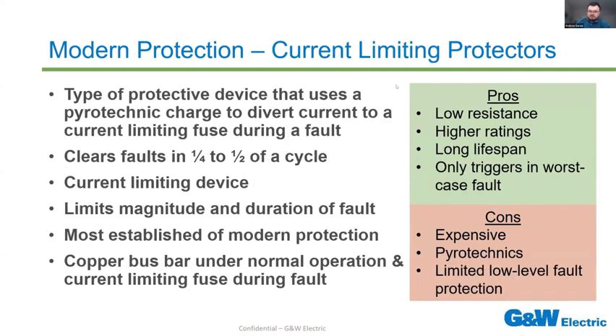Next, you have the current limiting protector. This is a type of protective device that uses a pyrotechnic charge to divert current to a current limiting fuse during a fault. It clears faults completely in 1/4 to 1/2 of an electrical cycle. It's a current limiting device that limits the magnitude and duration of the fault. It is the most established of these modern protective devices. It's been around for about 4 decades, but it's finding a wider audience now that the grid is going through these major changes.